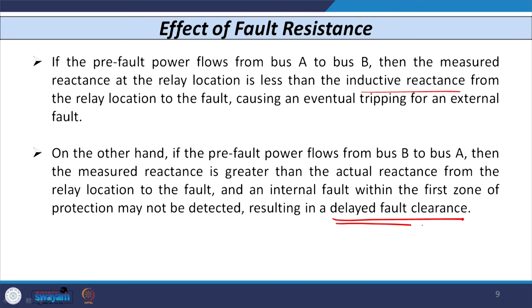The second case: if the pre-fault power flow is from bus B to A, then the measured reactance is greater than the actual reactance from the relaying point to the fault point. If any fault occurs within the zone of the relay, the relay is not able to detect that fault. That is known as underreaching of the relay, and it may cause delayed fault clearance, because that fault is seen in the second zone by some other relay, and that relay will operate after some time delay. So, this is a very important point.